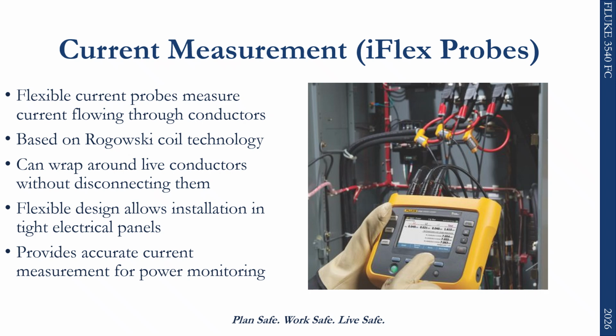The iFlex current probes are flexible current sensors used to measure the current flowing through electrical conductors. These probes use Rogowski coil technology and can wrap around live conductors without disconnecting them. Their flexible design allows installation inside tight electrical panels while still providing accurate current measurements for power monitoring.